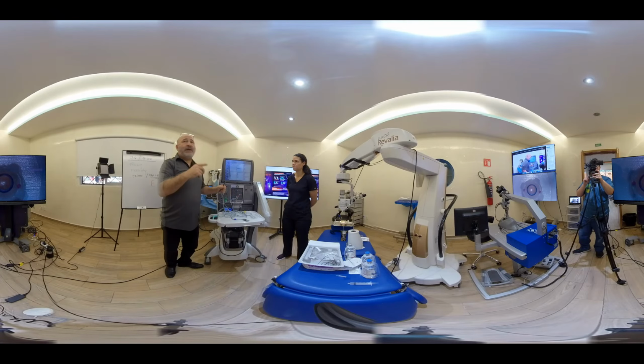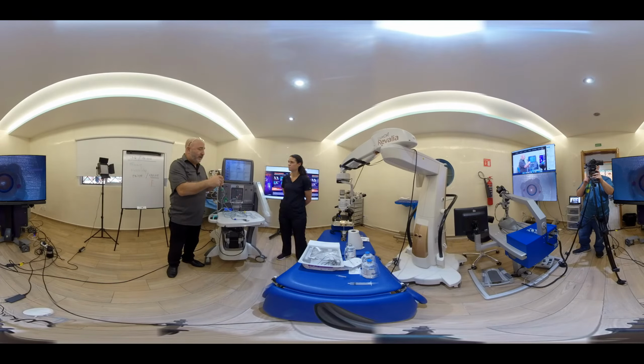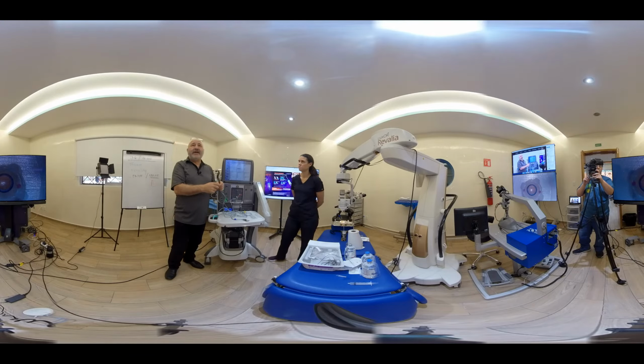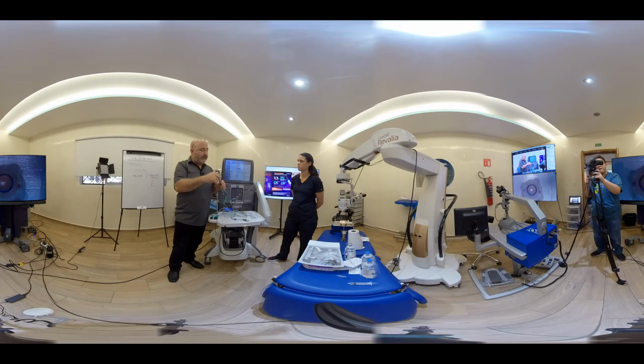Phaco tip. There's only one phaco tip for this machine I highly recommend. That's the Mini Tip 45 Full Kelman. And we can discuss later if you guys are interested. But I'm going to show you the old-fashioned way of putting a phaco tip on, the right way. Turn till it stops, and then it's 1, 2. And then underneath the wings, because this is where most people unscrew the tip without thinking. Get underneath it and pull it off, because you can easily unscrew it.